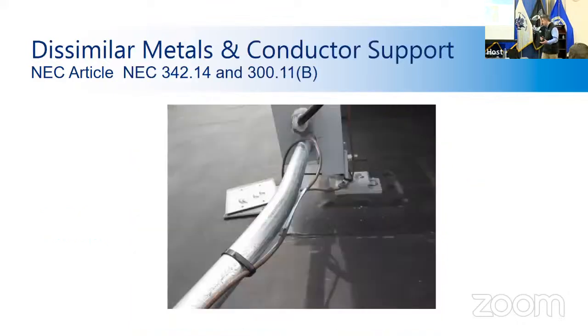Here, same problem. You can see it's corroding where it's in contact with the conduit. That's actually copper grounding wire. Eventually, that'll corrode through and it won't be connected to the grounding system. And also, according to code, you're not allowed to run grounding wire on conduit. I think you're only able to run communication or data wiring along conduit. It's very stringent on what kind of wire you're allowed to run along conduit.